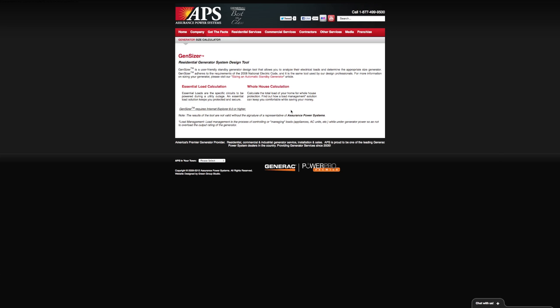Whole house calculation is used to calculate the load of your entire home, which is becoming the most common way to use a generator system because of load management. Load management is essentially the process of controlling or managing loads such as appliances and AC units while under generator power so we don't overload the generator system. This is actually a part of the new National Electrical Code.